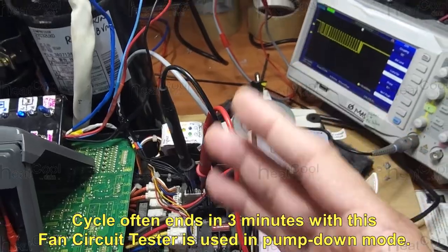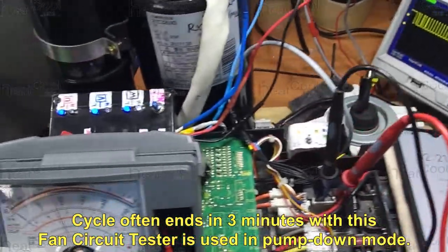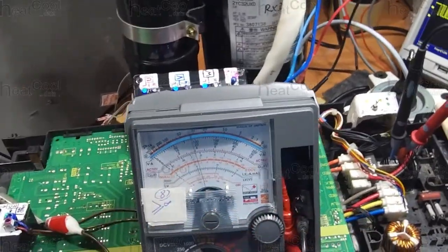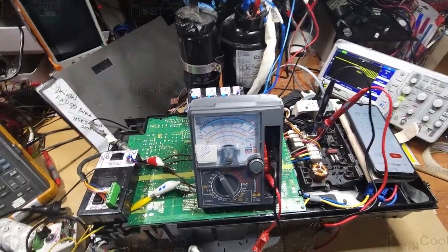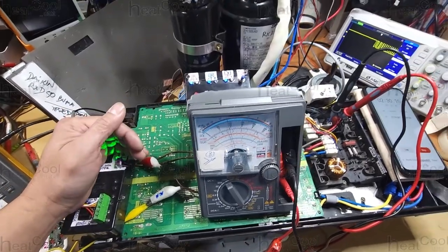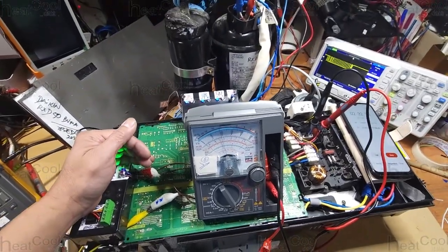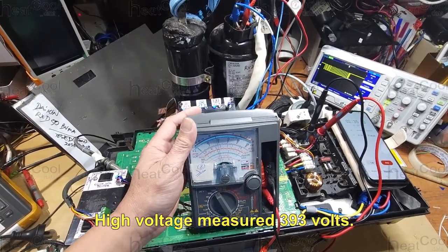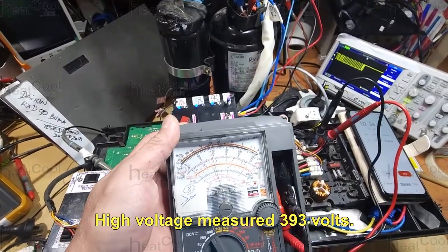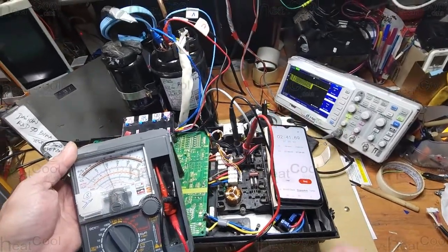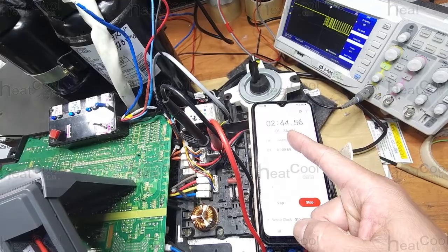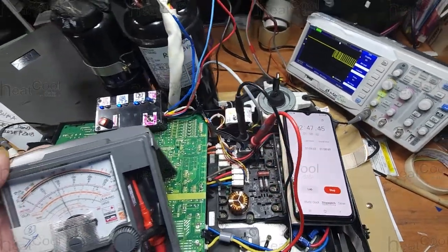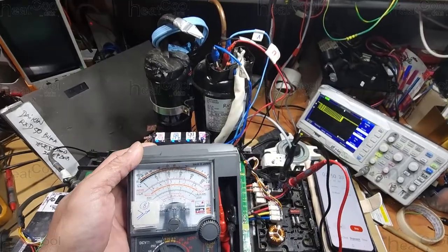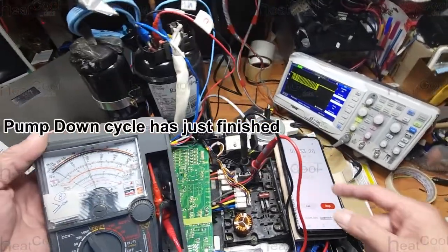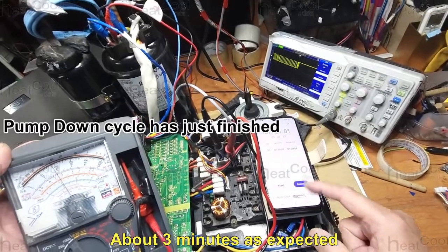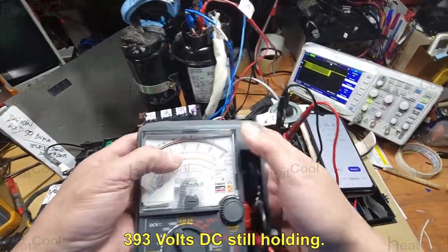More than 2 minutes now. The cycle often ends in 3 minutes when this fan circuit tester is used in pump-down mode. High voltage measured 393 volts. About 3 minutes as expected. 393 volts DC still holding.